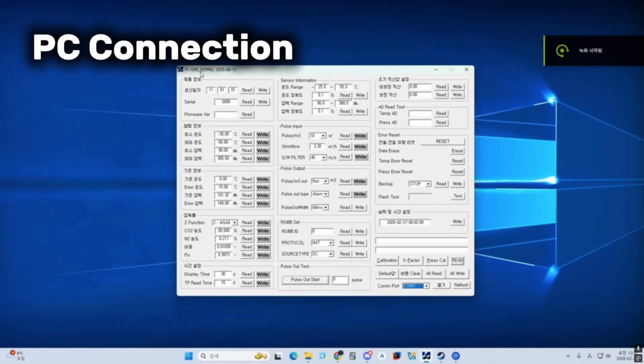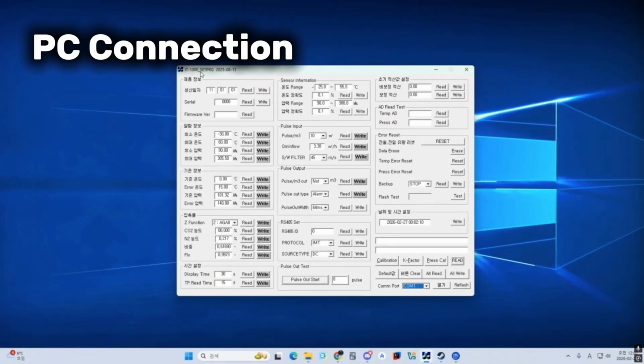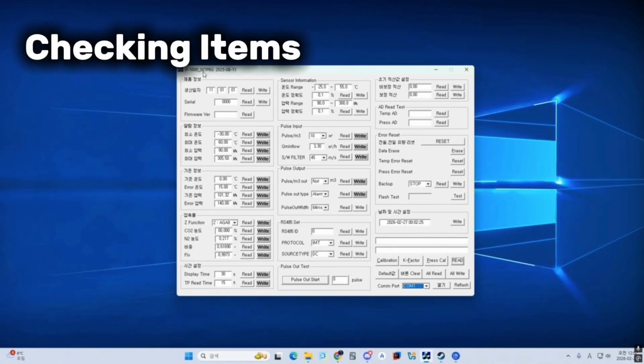Connect the IT1000 to your PC using the dedicated cable and run the setting program. This software allows you to check or update the device setting according to your field conditions. On the left side of the screen, you will see the read and write buttons. Click read to load the current data from the device onto your screen.